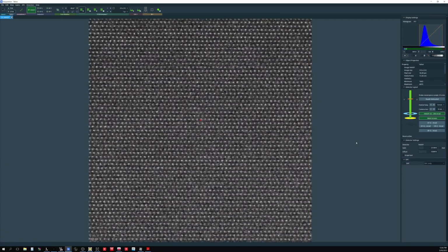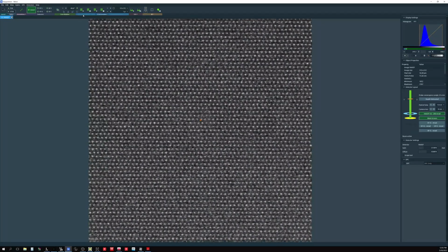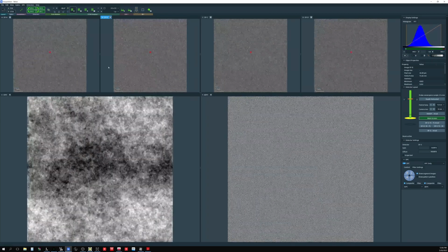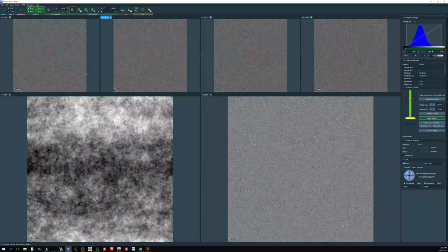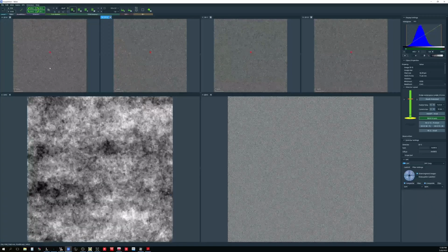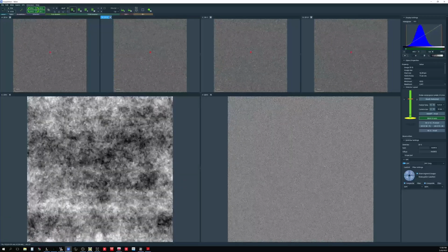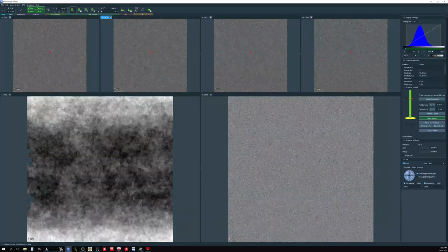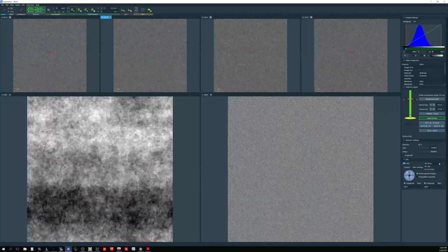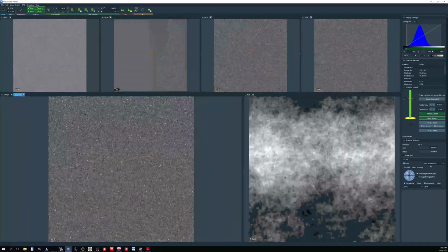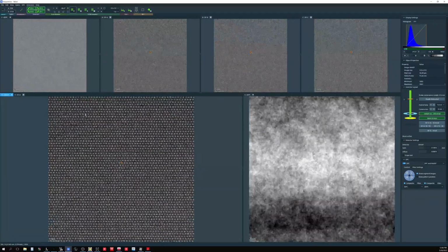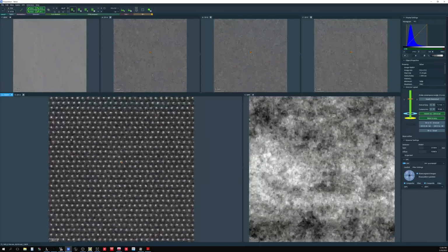To use the iDPC, we can stop the live scan for now, go to here, and turn on this DPC switch. And now you see basically six live scans. DPC quadrants A, B, C, D, and this one is for iDPC, this one is for dDPC. Here you can change this scan to DPC and HDF. So now we can also get HDF signals.